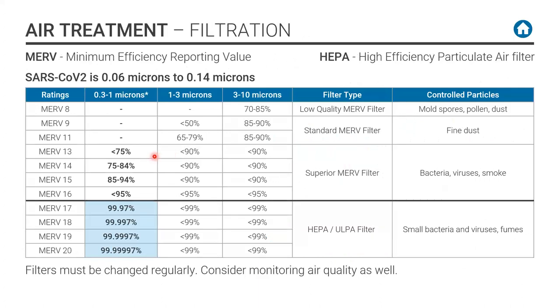So let's talk about filters. Again, ASHRAE charts. Filters are rated by what they're trying to capture. And the standard ASHRAE charts talk about a few things. There's MERV ratings, and everybody knows what MERV is today. You can go from MERV 8 to MERV 20 filters, and then ASHRAE rates them on what they're trying to capture, 3 to 10 micron particles, 1 to 3, and it goes down to 0.3 to 1. Now, if you remember, I talked about the virus being around 100 nanometers or 0.1 micron, and you might say, whoa, this is being rated at 0.3. The virus is much smaller. You said it's 0.1. Well, we'll talk about that in a second.